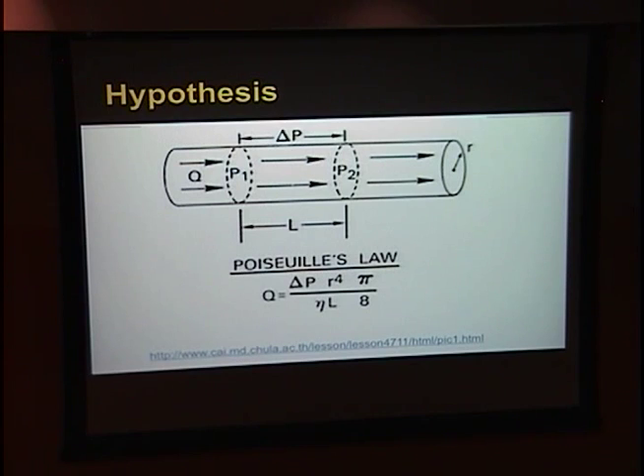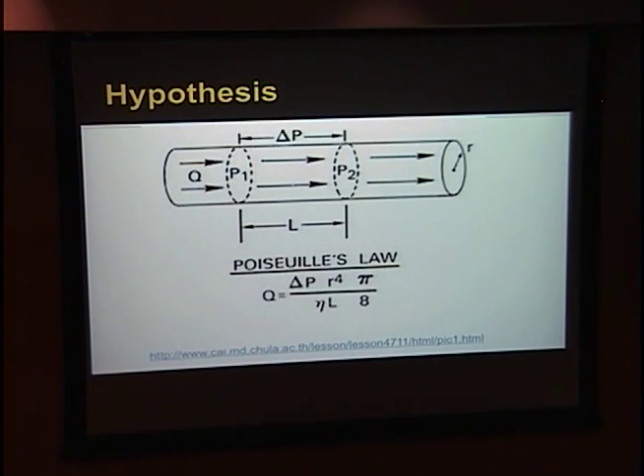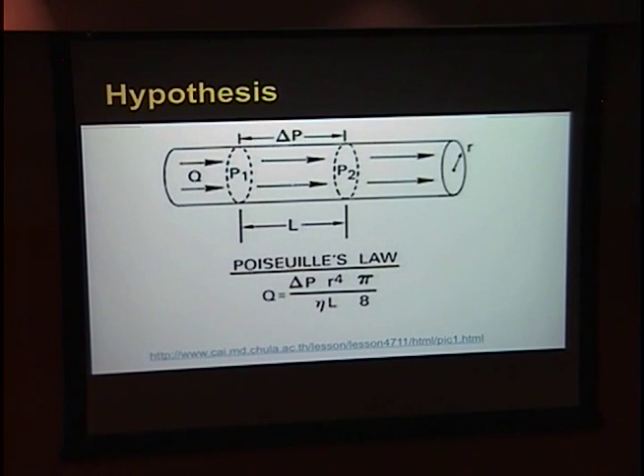Vacuum levels also play an important role in the extraction process. The total hold for any given level of vacuum would be highest for a large bore tip, given that total hold is directly related to the square of the bore size opening. We ran 24 runs of extraction with each phaco tip and took the best 20 results.